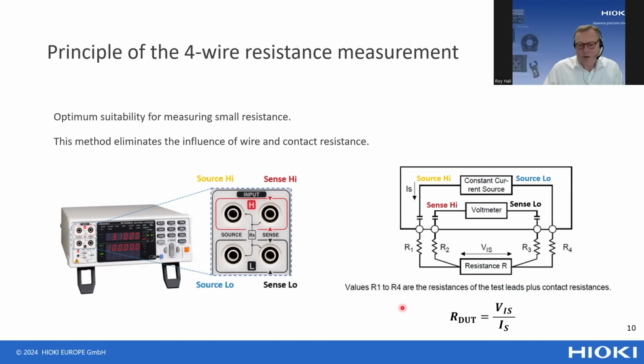As the resistance of a lithium-ion battery is just a few milliohms, sometimes more, sometimes less, it is necessary to use a 4-wire measuring principle. This method eliminates the influence of the connection resistance, which consists of the wire resistance and the probing resistance. The connection resistance is much higher than the internal resistance of the battery, and therefore it needs to be cancelled out to have an accurate measurement.